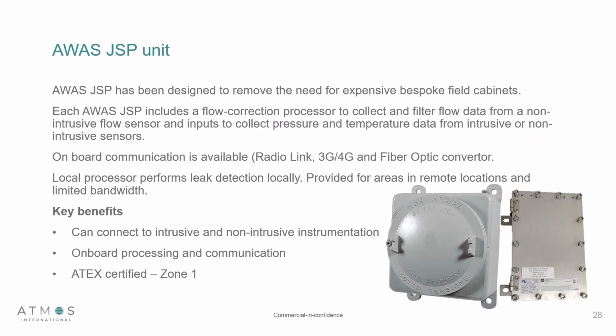As well as the Eclipse unit that allows us to connect to pipelines that previously didn't have instrumentation, and we no longer have to have the concern of asking for new tapping points, we've also developed what we call the JSP unit. This is designed to remove the need for very expensive bespoke field cabinets, and all we do is take a cabinet that we need for leak detection purposes. So each AWAS JSP includes a flow correction processor to allow us to collect flow data from non-intrusive flow sensors, and it allows us to collect pressure and temperature from intrusive or non-intrusive sensors. The onboard communication is again the same as the Eclipse unit.